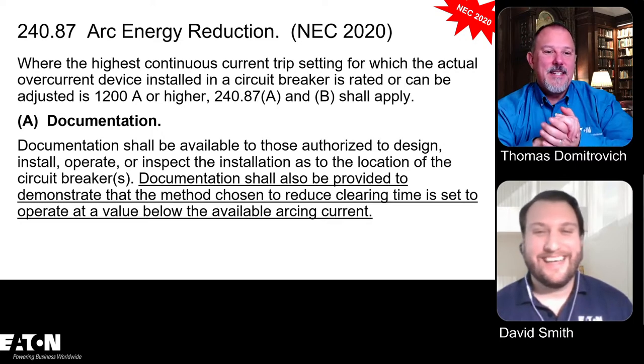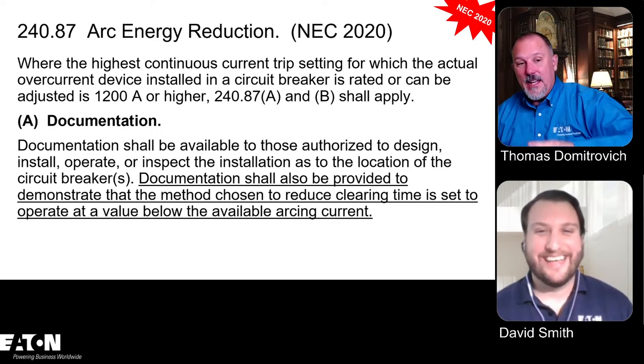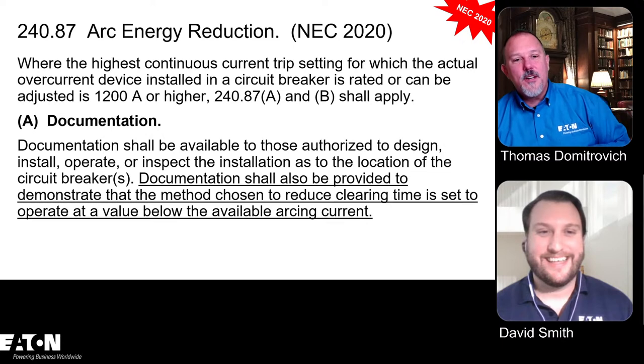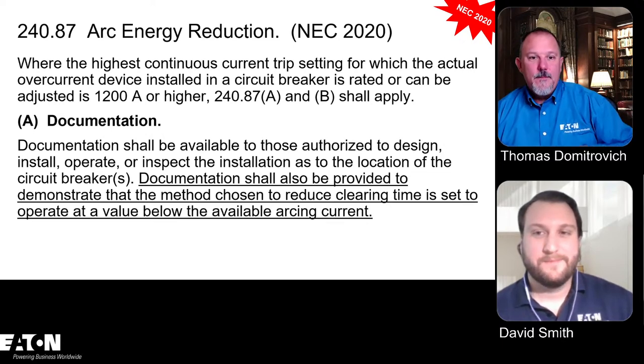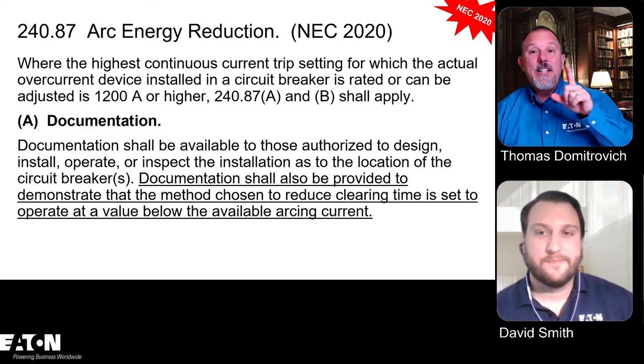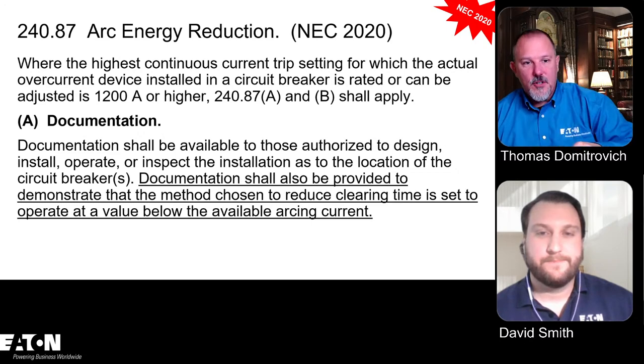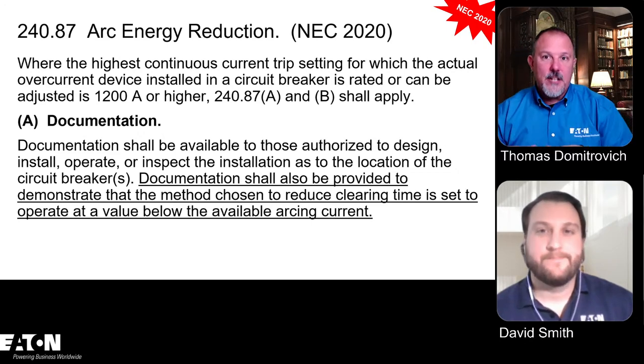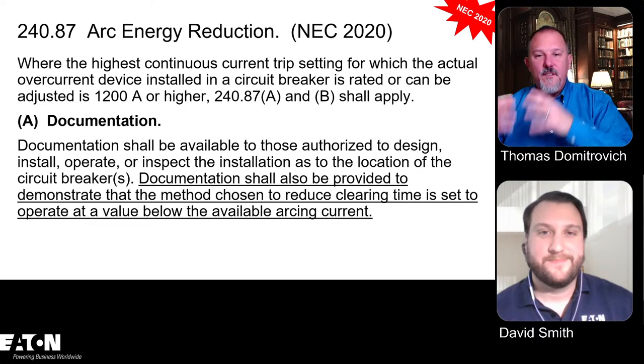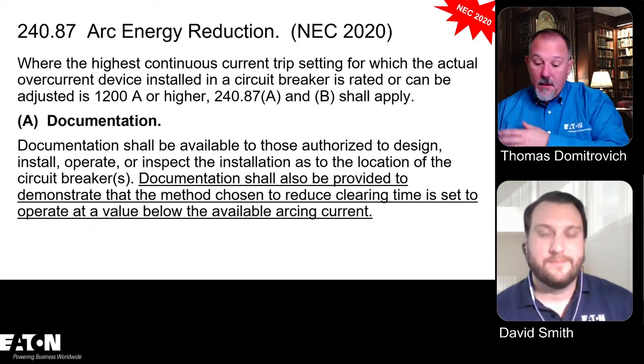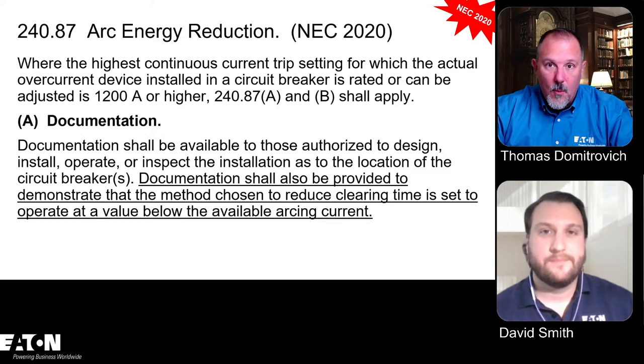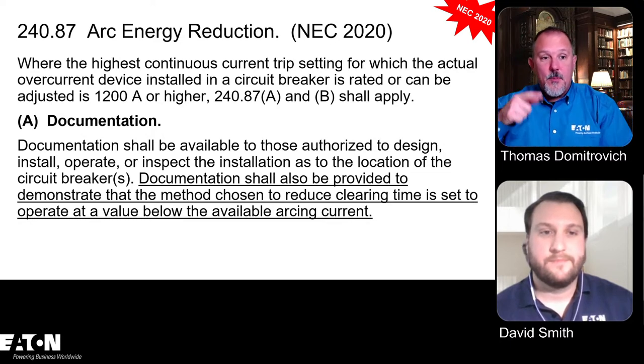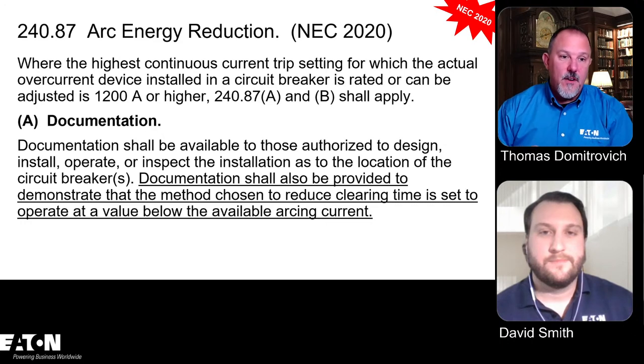Now, Robert says 70E does not define arcing current. Right. They don't define arcing current, but they do define available fault current. And that's where the National Electrical Code got it from. So available fault current was defined in 70E. Available fault current was then put into Article 100 to align with that. And they put the same image on available fault current.